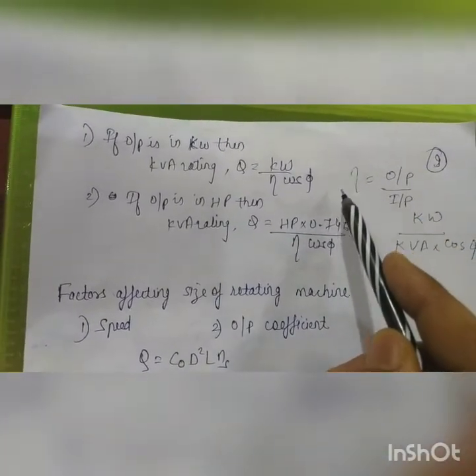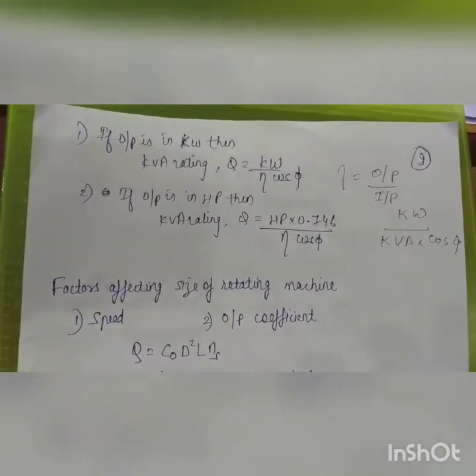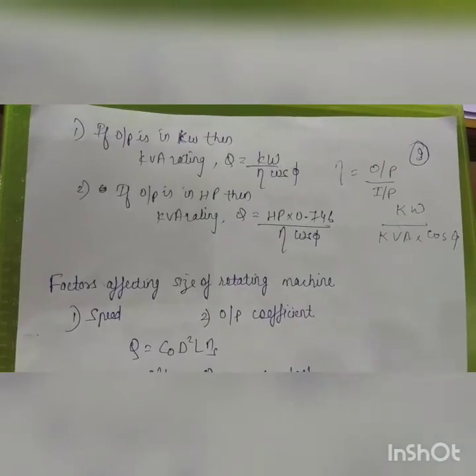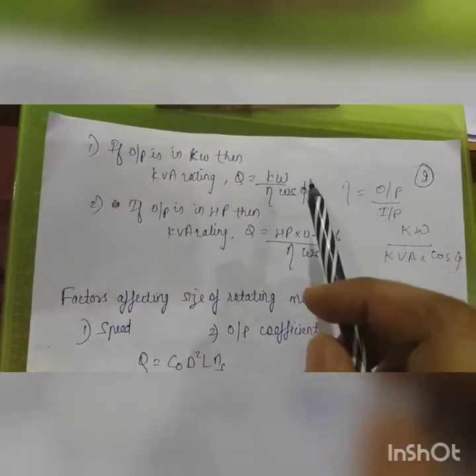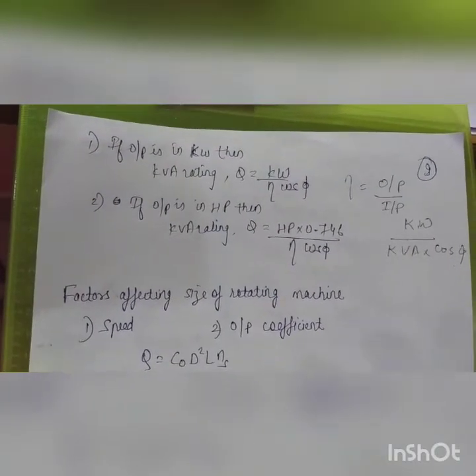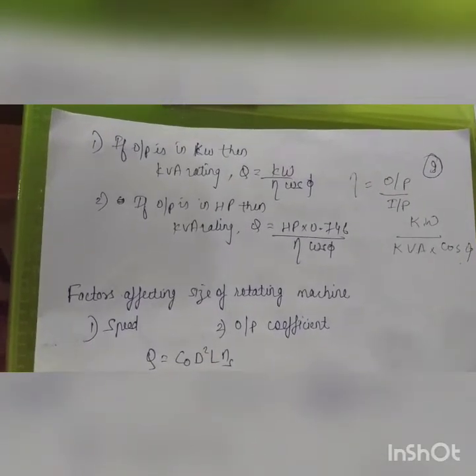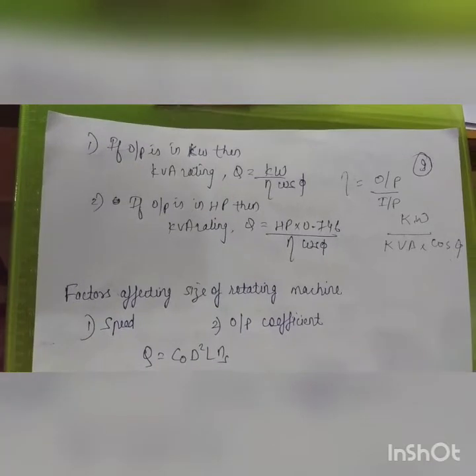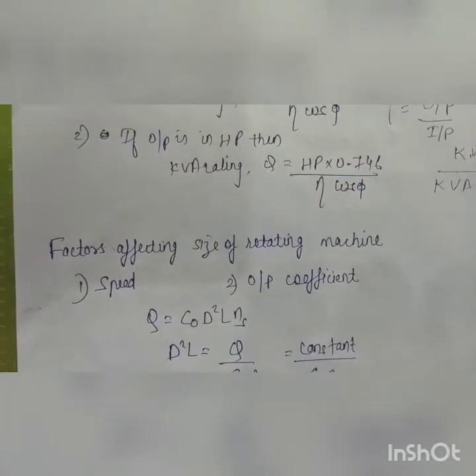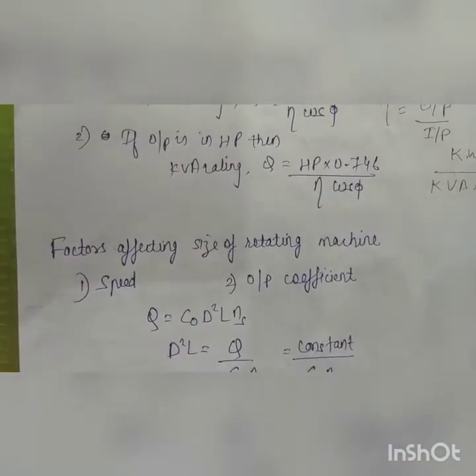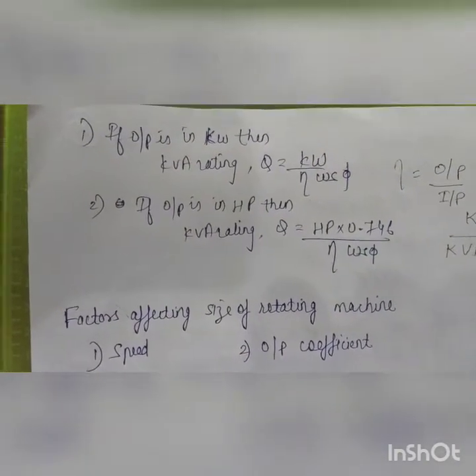Efficiency equals output power divided by input power. Since output is in kilowatts and input equals KVA times cos φ, rearranging gives Q = kW / (η · cos φ). So if output power is given you can easily calculate the KVA rating. If the output is in horsepower, first convert: multiply HP by 0.746 to get kilowatts, then apply the same formula.